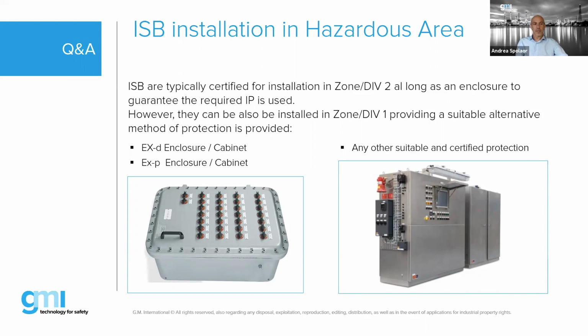Yeah. Okay. So the answer, of course, depends on certification. So also the variable frequency drive or any kind of device must be suitable for installation in that area, and the certificate must be clear for that device. Of course, Zener barriers and isolators basically can be installed in zone 2, but that must also be clearly stated on the marking in the certificate for the isolators or the barrier. So in this case, you must check the certificate.